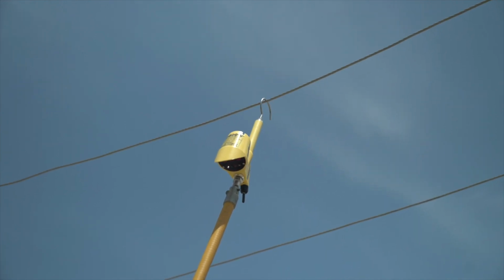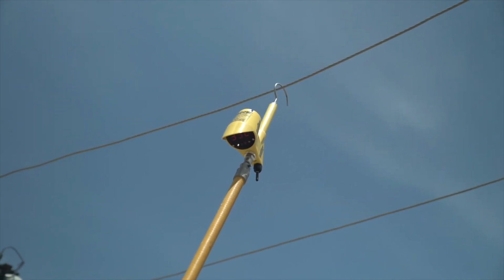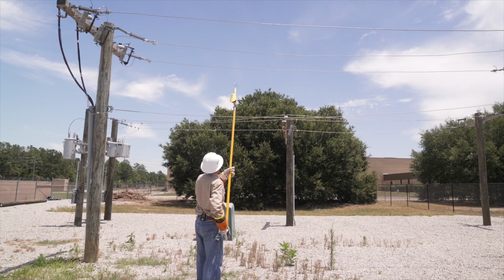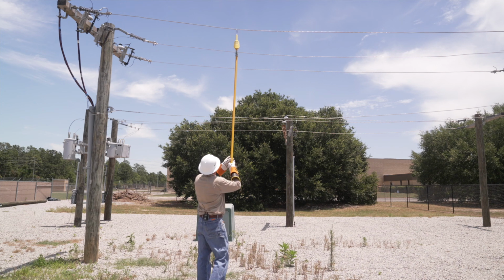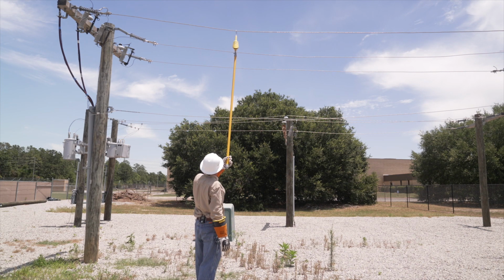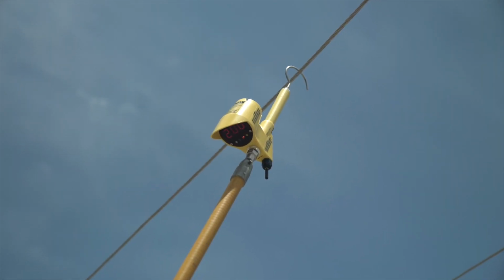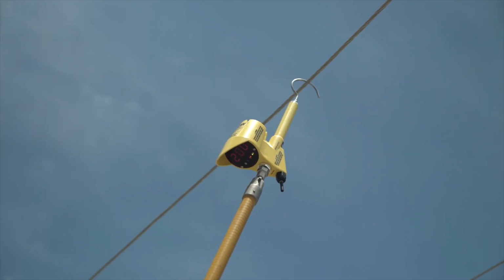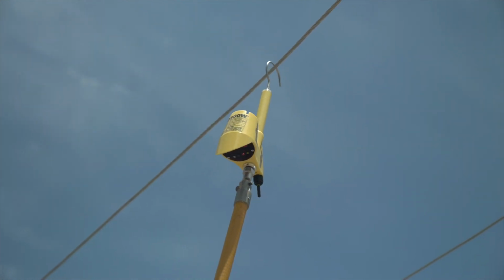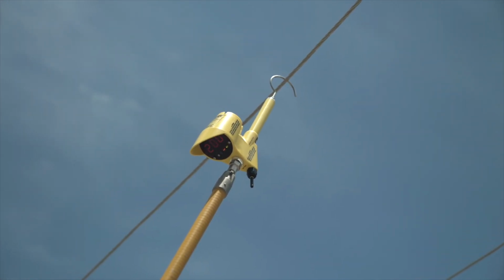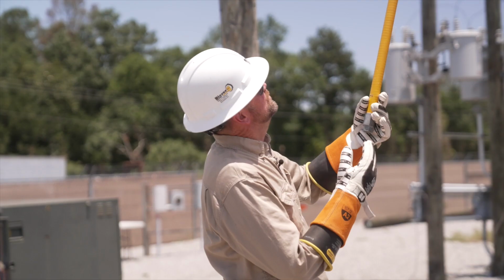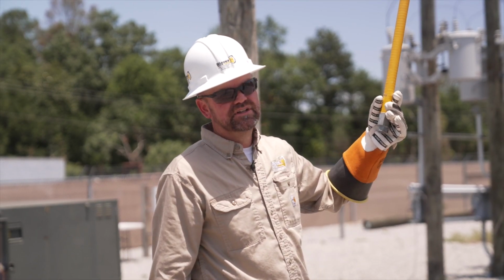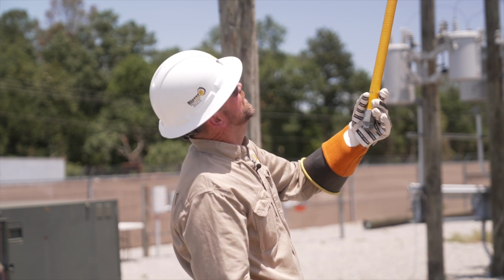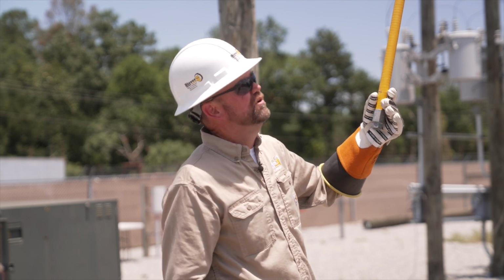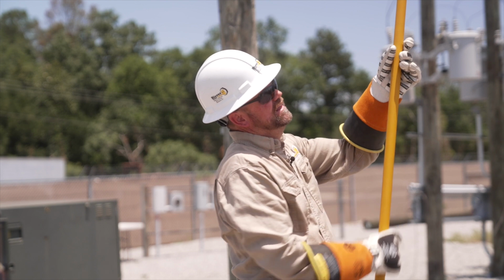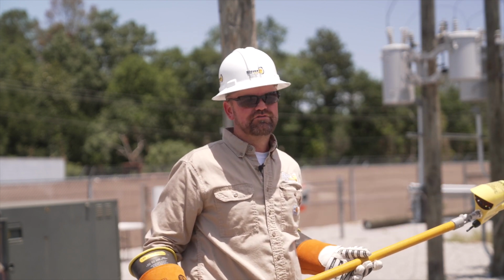I have my white light near 0. So this in fact is the phase that my reference probe is on. And on my outside phase, I've done something here where it demonstrates some of the situations you may encounter in the field. I actually have a de-energized phase. On my switching cabinet that feeds this overhead conductor, I have this phase de-energized, and it demonstrates some of the weird phase angles you can get. In other words, this phase is getting induced a potential from the middle phase. So the phase angle is not pretty. So this is telling me that something is wrong. Basically what I would do in this situation is ride back and determine where this becomes a 240 solid red light.